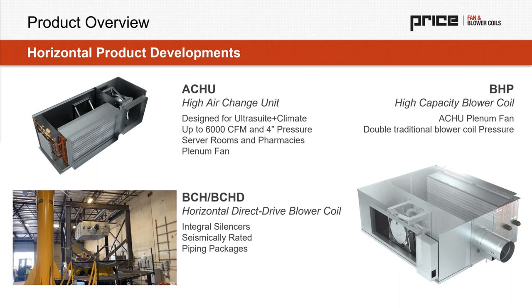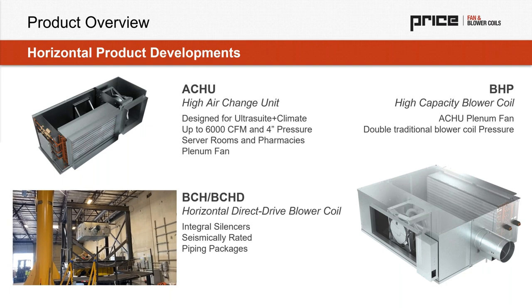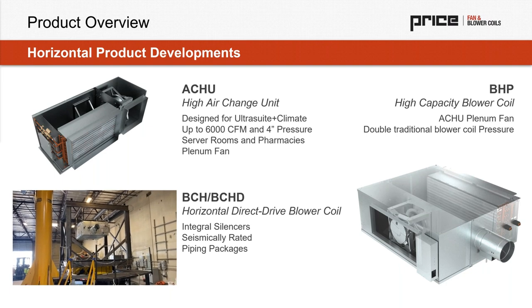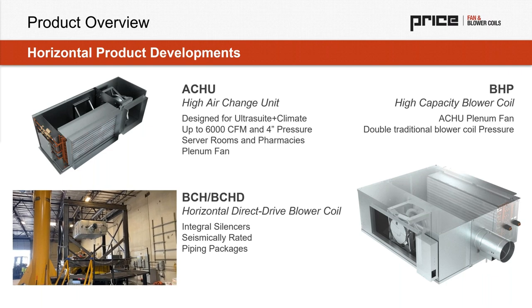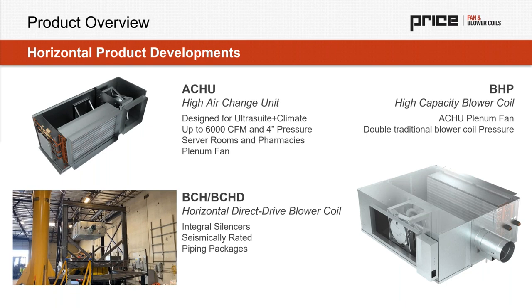One that we'll be releasing this year, which is also getting used on a St. Jude's Hospital project, as well as some large tower projects in downtown Los Angeles, is what we're calling our BHP model, which is using a plenum fan. So the real point of that product is you can almost think of it as custom indoor air handler operation, but at about a quarter of the price point. The other main application we imagine seeing that used is with DX coils as a split system indoor air handler. That will serve up to 6,000 CFM and is really double the static pressure of a traditional blower coil at half the acoustical output and far less power consumption.